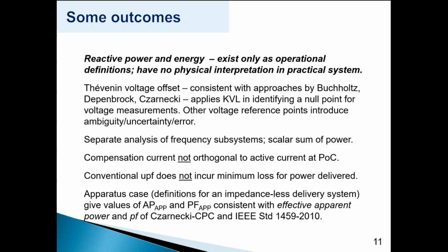So those other voltage reference points, including a neutral wire, introduce ambiguity and uncertainty and error in making measurements. In other words, the measurements are not physically interpretable. They are measurements, that's fine, but you can't say it has anything to do with the power flow in the network. As I mentioned, because we separate the whole system into the frequency subsystems, we get the scalar sum of power. So the power at DC plus the power at fundamental frequency plus the power in the second, third, fourth, and fifth harmonics can be added, taking into account their direction, positive or negative. Positive power flow is into a load. Negative power flow is out of a source. And that's all. Power can't have a direction orthogonal to the wire. It can either go into the load or out from a source.